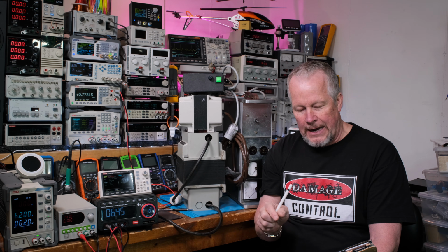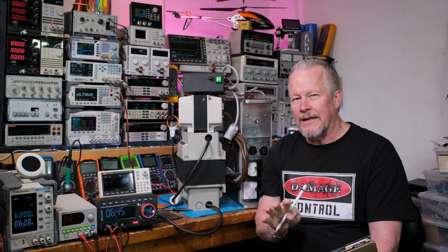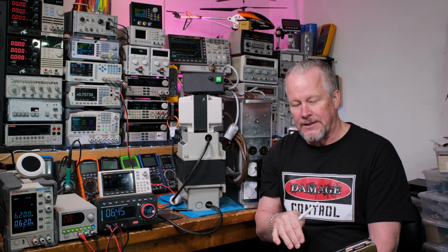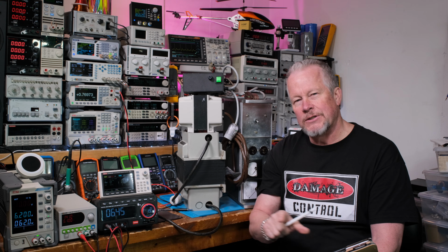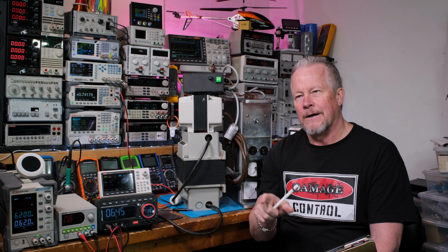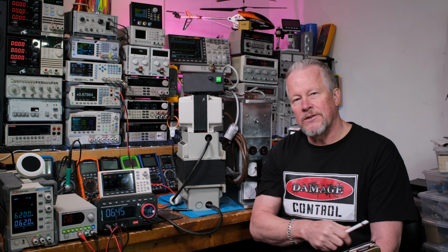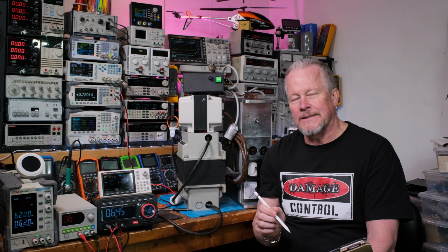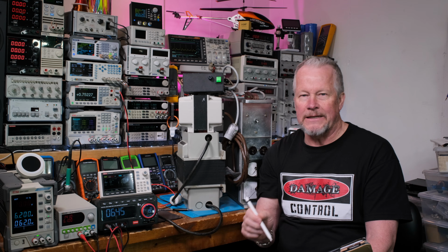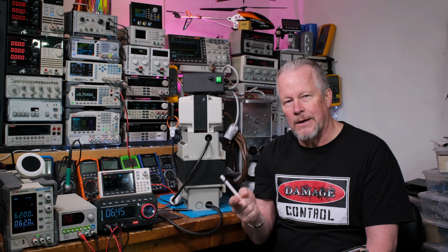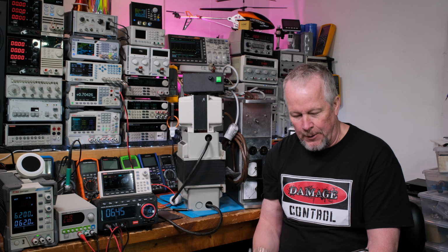So even though you have magnetic coupling, you also have capacitive coupling. This means you can have voltage potential on your secondary side because of your primary side, due to that capacitance. You can discharge that capacitance into you if you touch the wrong thing. So anyway, you just have to be aware of that.